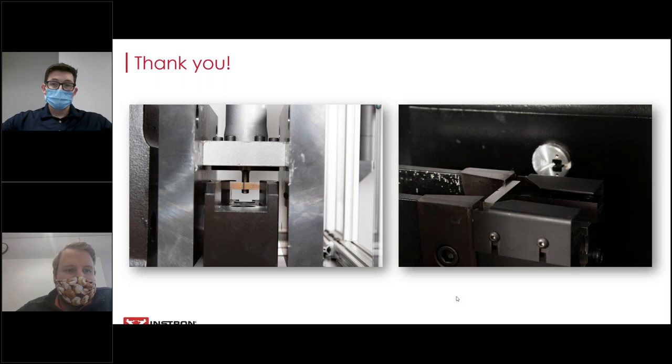Thank you. We have one here about how the specimens are made, specifically the notches. There are options. You can mill your specimens yourself. You can buy a miller, which is just a device to notch your specimen. Or, through the NIST verification program, you can purchase specimens, and it's a very fine precision technique and procedure that they go through if you want to notch your specimens.